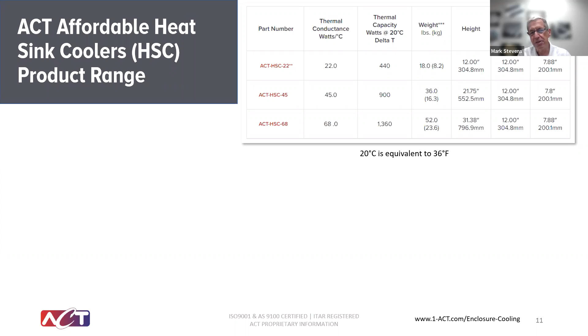So if you have a 20-degree difference between the inside and the outside of your cabinet, an HSC 22 cooler is capable of 440 watts of cooling. A quick way to look at that is if the differential is only 10 degrees, that same cooler is only capable of 220 watts, or half of the 440. So it's pretty easy to specify if you know what your internal heat loads are. And we have ways of calculating that coming up as well.